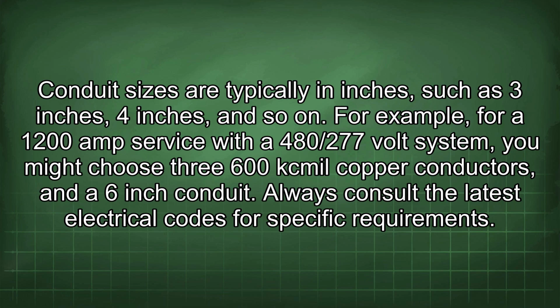For example, for 1200 amp service with a 480/277 volt system, you might choose 3 600 kcmil copper conductors and a 6-inch conduit. Always consult the latest electrical codes for specific requirements.